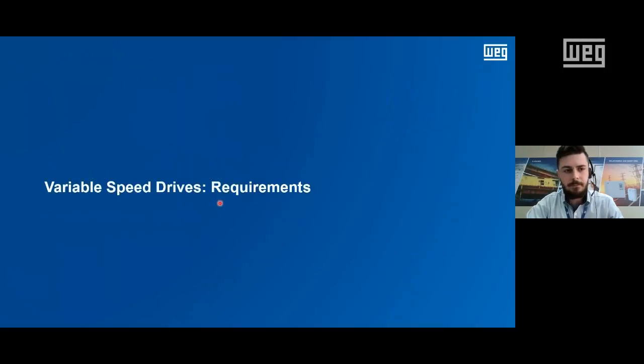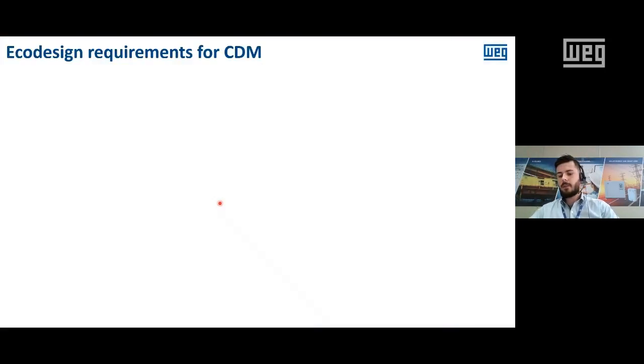Okay, so let's talk about the requirements. We know what products are in the scope of the regulation and the directive. Now let's understand, if your product is in the scope of the regulation, what are the requirements for this product? So the main requirement is that the CDM, the complete drive module, or a variable speed drive, must be IE2, the efficiency level.